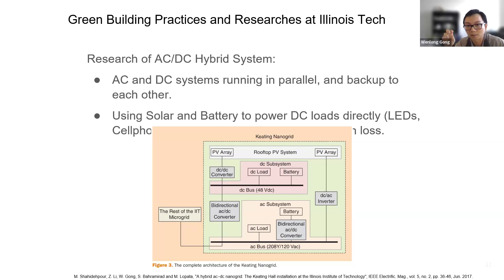If we generate DC, convert it to AC to send to the customer, and then the customer converts it back to DC for their devices, there are two conversions and energy is lost both times. So the idea is to power DC loads directly with DC. We have PV arrays directly powering the LEDs in our gymnasium at Keating Hall, also charging the battery when there's excess energy not used by the lights, and at night the battery powers the lights. The DC and AC systems are coupled through a bidirectional AC to DC converter, so on a cloudy day the AC system can still convert to DC to support the DC buses.